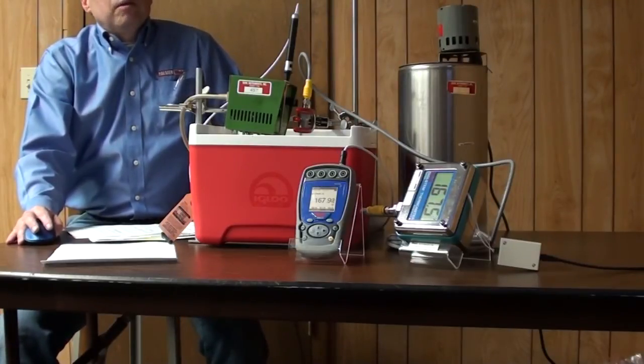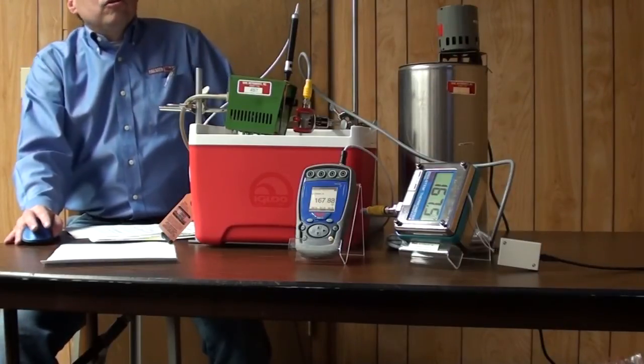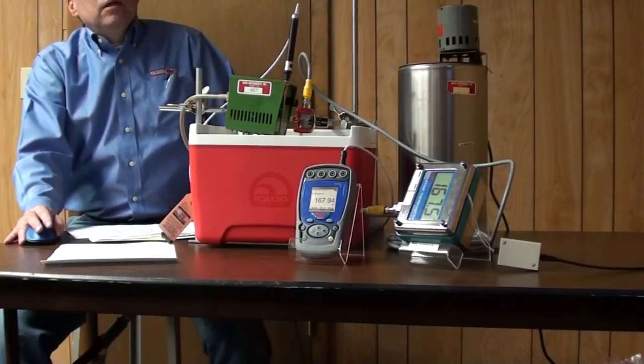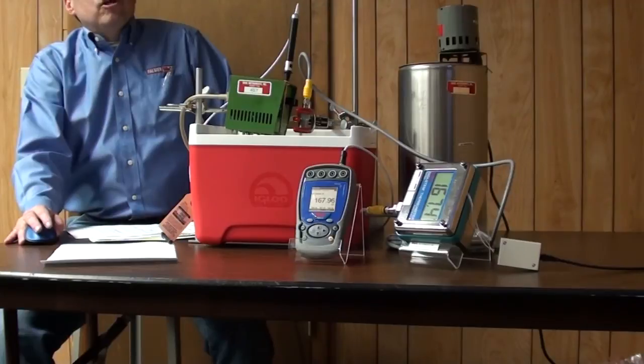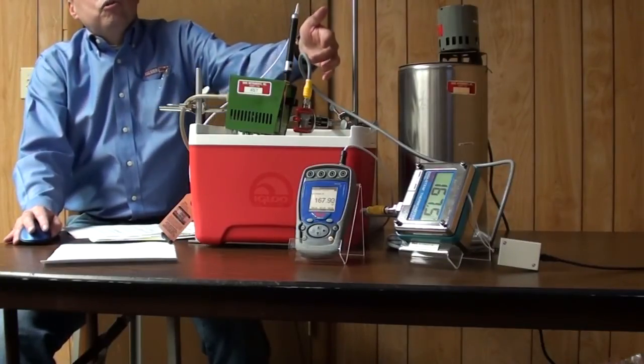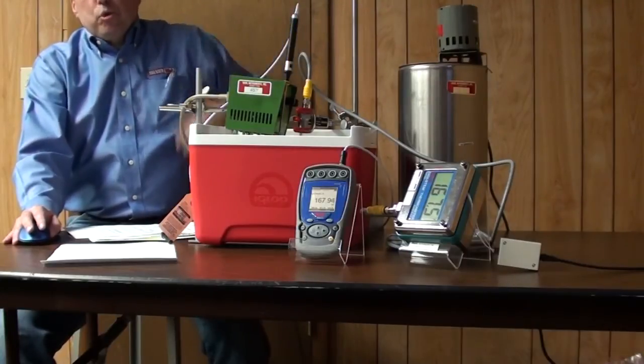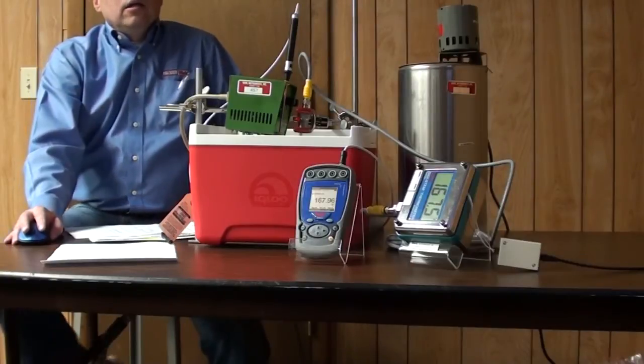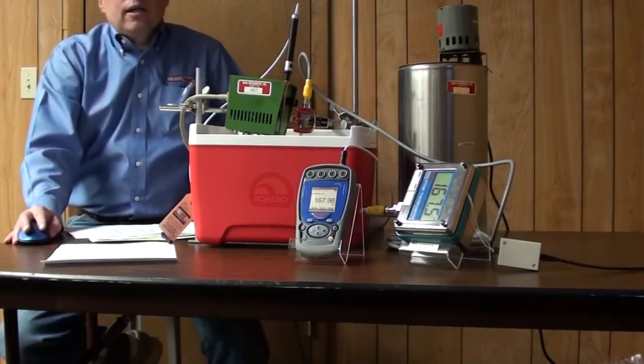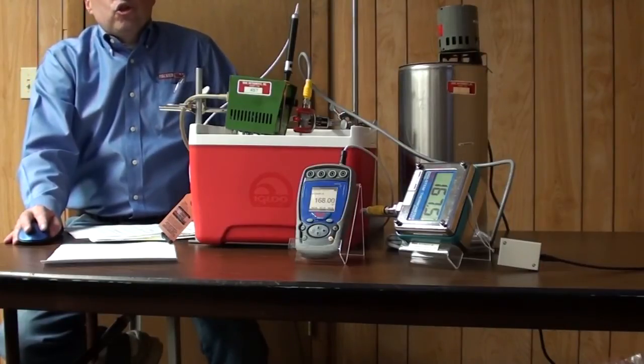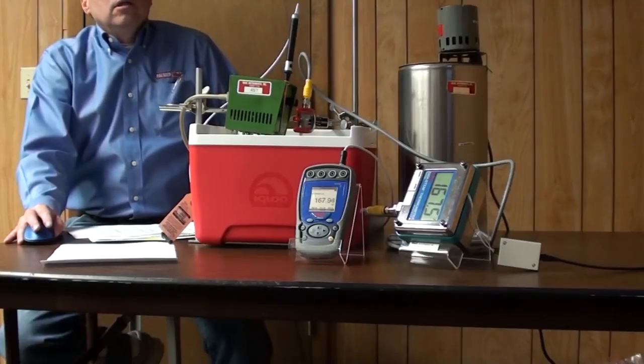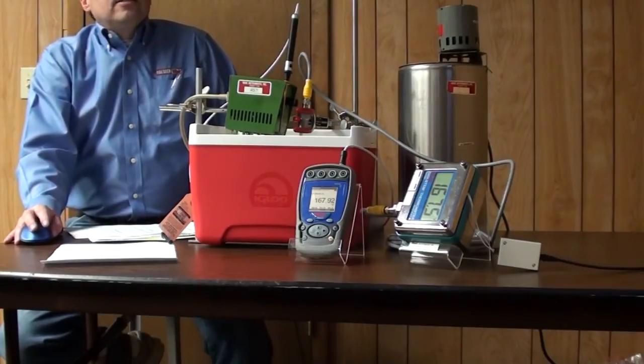We have a warning on ours, and then basically we go through, and I'm not going to go through all this in detail. You will get this and can review it, but for setup, we do allow a 15-minute stabilization period. And the other thing is we want to make sure these probes are installed to about a 4-inch depth or more. Certainly if it's a longer probe, you can do more than that. But due to the temperature conductivity up the stem, when you start doing lower immersions, you may affect the accuracy of that calibration. And then this is the data collection here. It's just giving some instructions on that. Here we talk about before data, and then we're going to record all that data in the appropriate places, and we'll discuss that when we're actually doing the calibration.